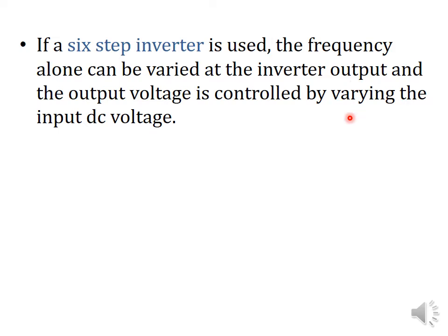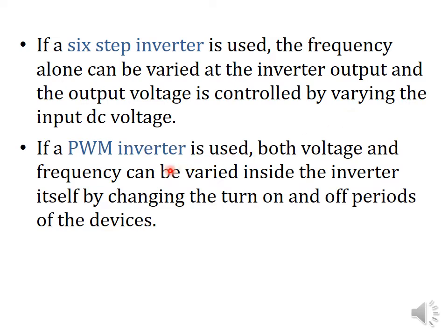To control voltage with a six-step inverter, we have to supply a variable voltage input to it. If a PWM inverter is used, then both voltage as well as frequency can be controlled inside the inverter itself by changing the turn-on and turn-off periods of the devices.